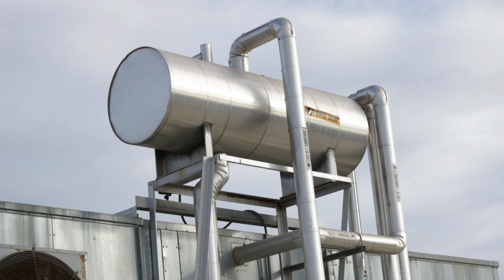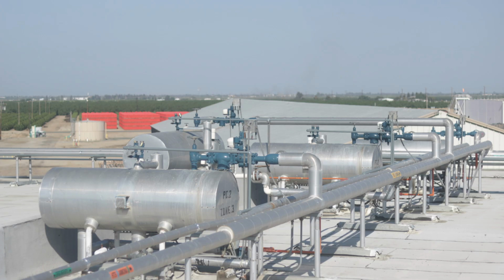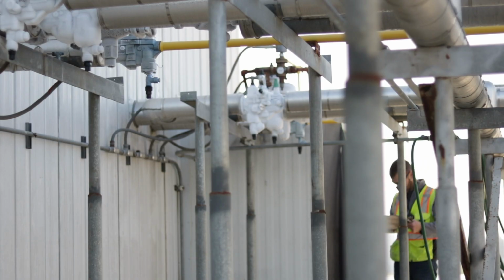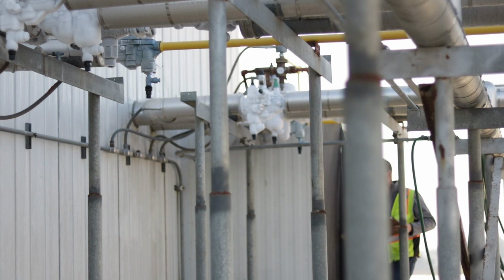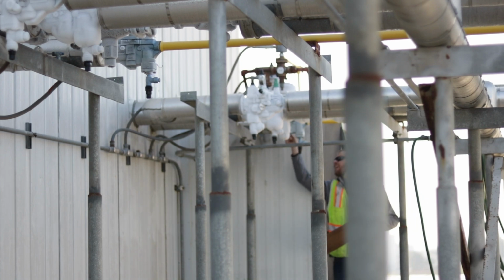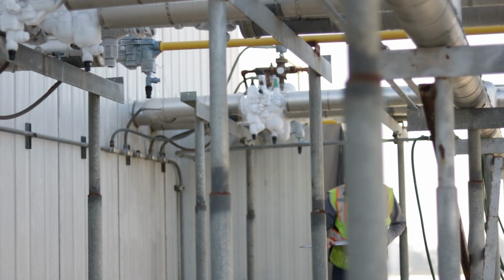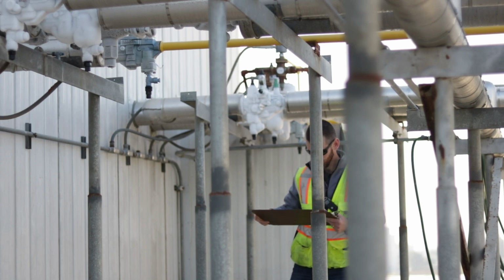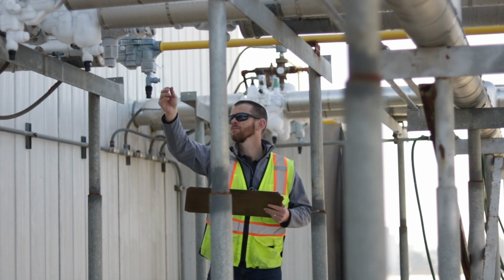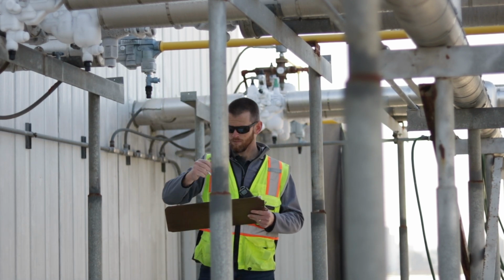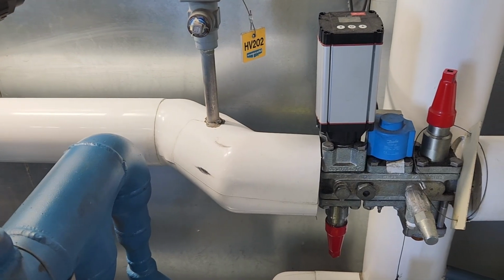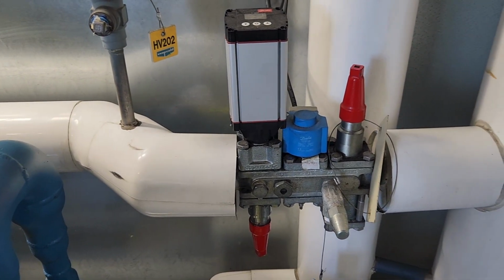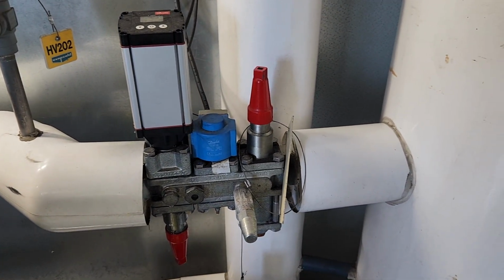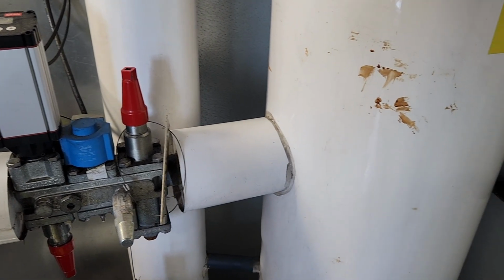In gravity-fed or flooded systems, the solenoid valve will be interlocked with a float switch or level probe on the surge drum. In direct expansion or pumped overfeed systems, the solenoid valve may be controlled by the room temperature. Either way, the operator must ensure the valve stem is in the automatic position before starting the evaporator. Other control valves, such as motorized expansion valves and inlet pressure regulators, must also be correctly positioned prior to startup.